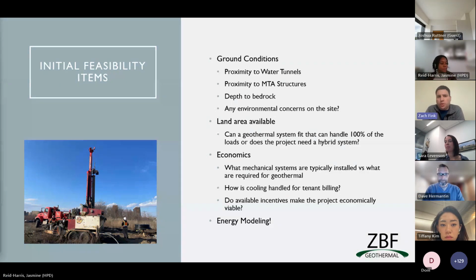With bedrock, you either want relatively shallow bedrock - we typically say under 100 feet deep - or you want relatively deep bedrock, where bedrock is deeper than the depth of your boreholes. You'll find both in New York City: more in Coney Island and the Rockaways, that's unconsolidated, where bedrock is 400, 500, 600, 800 feet deep. And then in Brooklyn and Manhattan, you might find bedrock 25 or 30 feet deep.